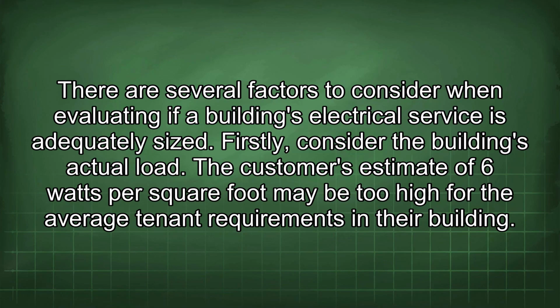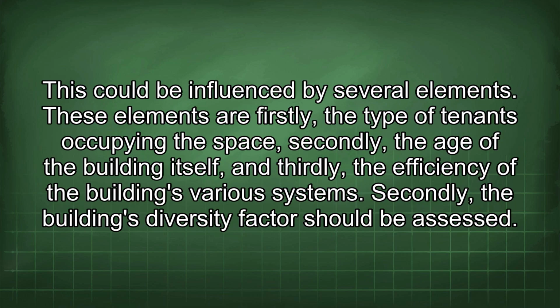There are several factors to consider when evaluating if a building's electrical service is adequately sized. Firstly, consider the building's actual load. The customer's estimate of 6 watts per square foot may be too high for the average tenant requirements in their building. This could be influenced by several elements. These elements are firstly, the type of tenants occupying the space, secondly, the age of the building itself, and thirdly, the efficiency of the building's various systems.